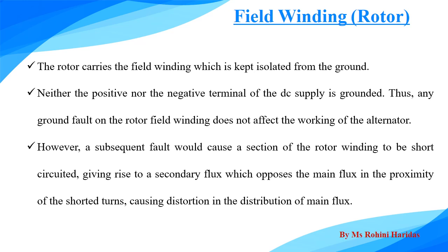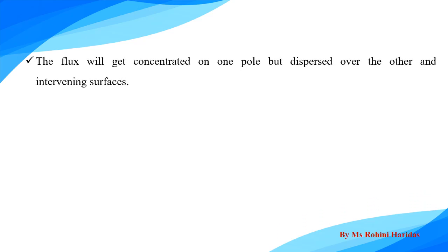However, a subsequent fault would cause a section of the rotor winding to be short-circuited, giving rise to a secondary flux which opposes the main flux in the proximity of the shorted turns. It will cause the distortion of the distribution of the main flux.